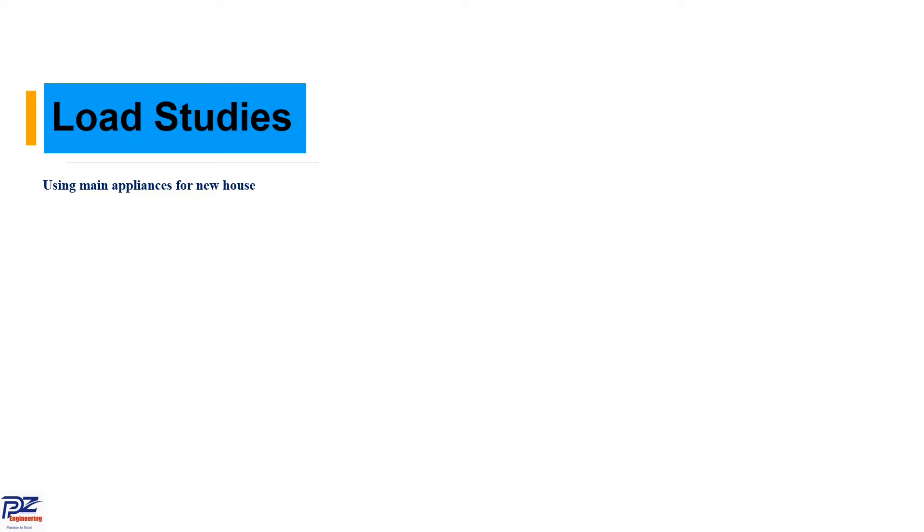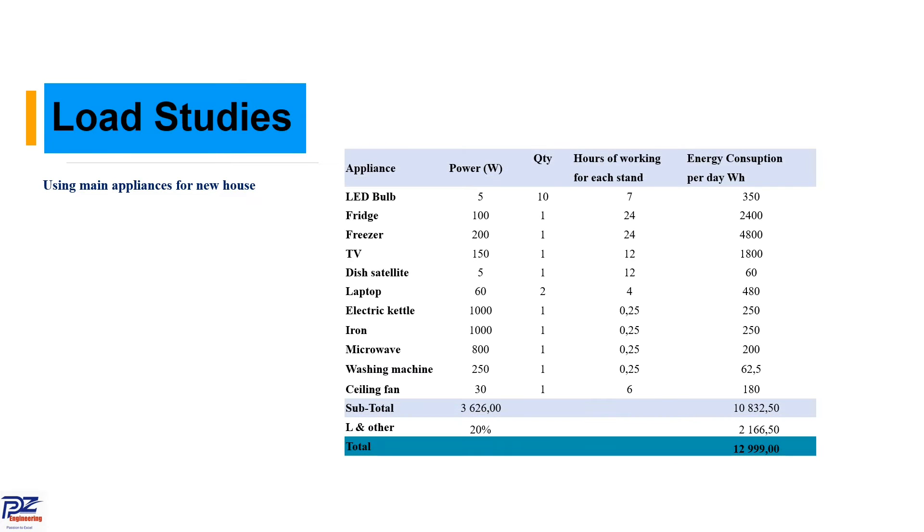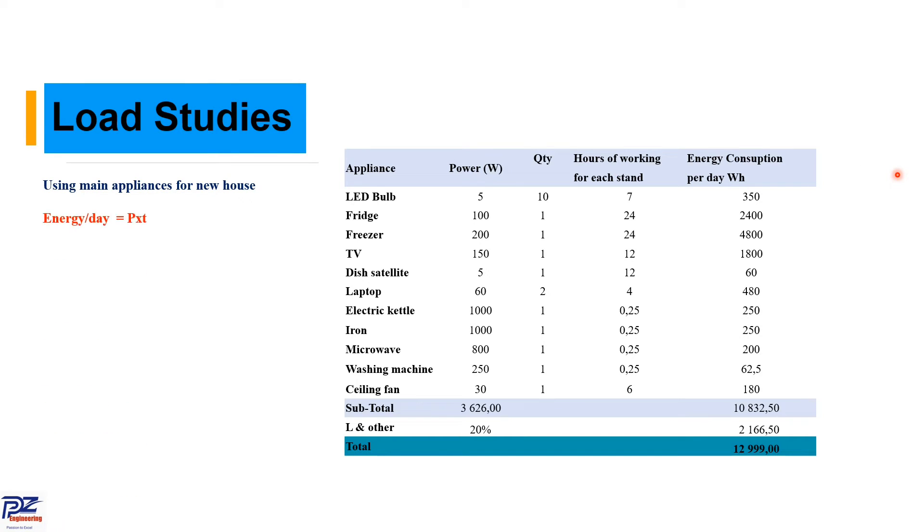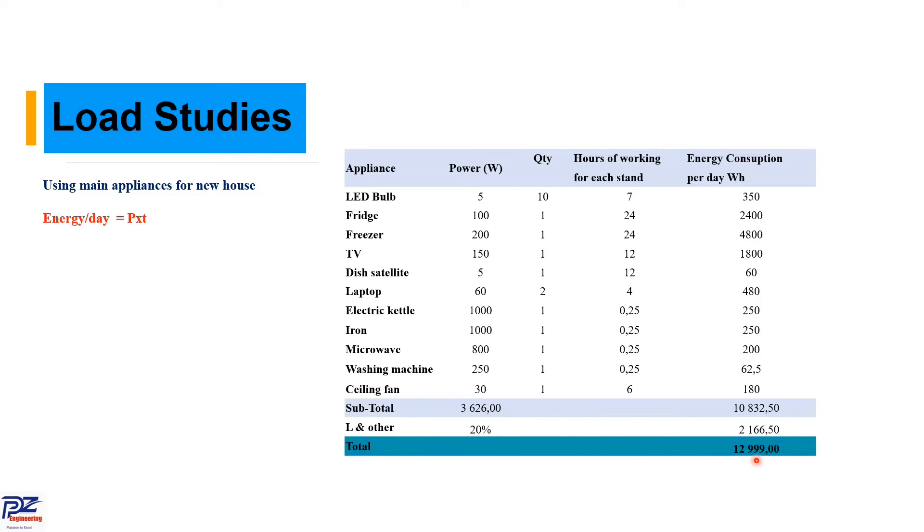The first step is our load studies. We can use it for a new house or existing house. For new houses, we are going to estimate based on the appliance that might be used. This table shows our appliance, power demand, quantity, working hours and energy consumption. We find energy consumption per day by power times time times quantity to get the total power of the house. You can follow as it is.